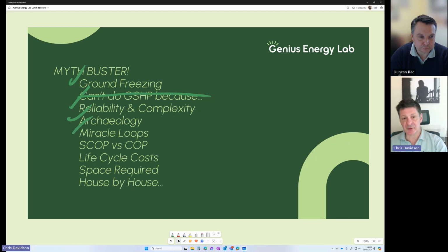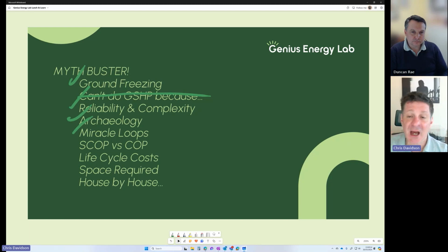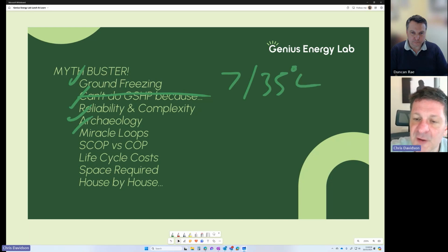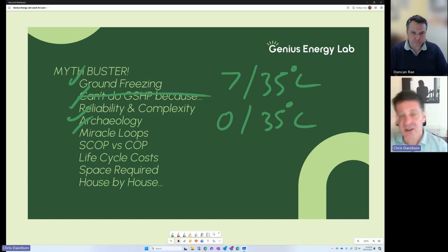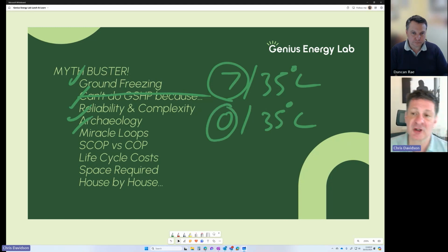COP and seasonal COP is a much vexed topic. People are using COP, coefficient of performance, which is how much heat do I get at a specific condition divided by the electrical consumption. Now that specific condition for air source is 7 degrees on the source and 35 degrees on the load, and for ground source, it's 0 degrees on the source, 35 degrees on the load. It's not an equal playing field. That's more like an average air temperature in the UK, and that's a minimum water temperature for a ground source in the UK. And so it's not a fair playing field.